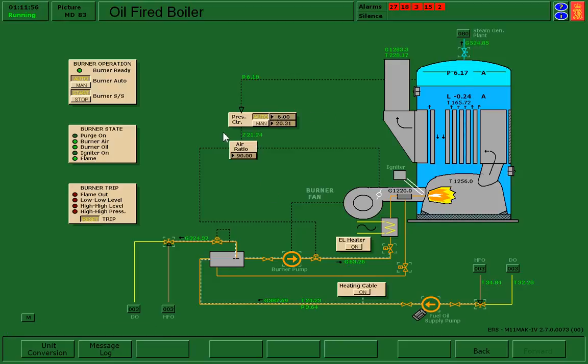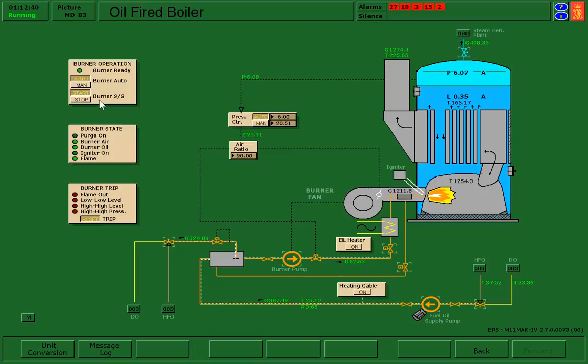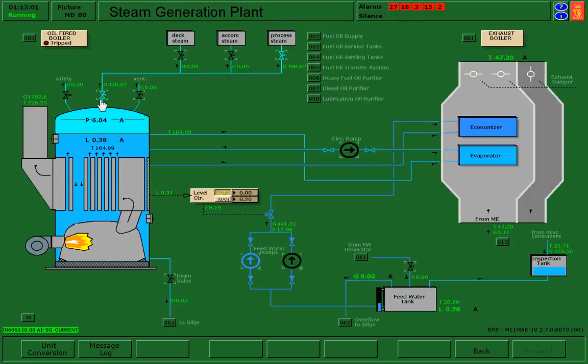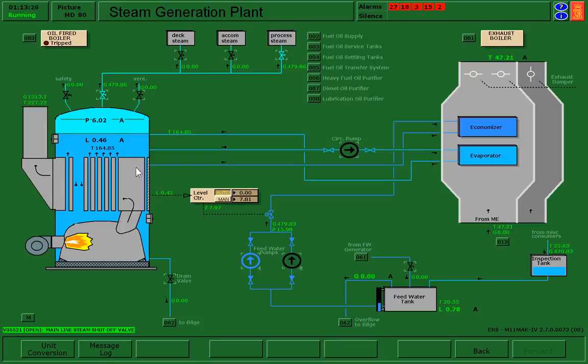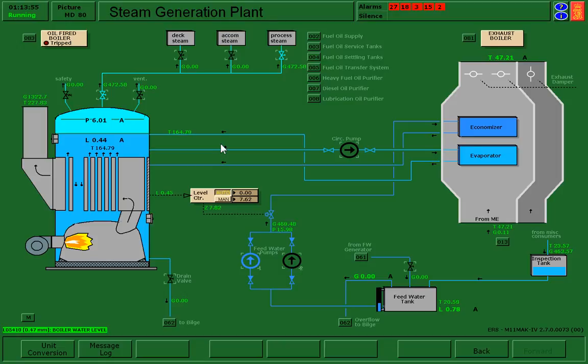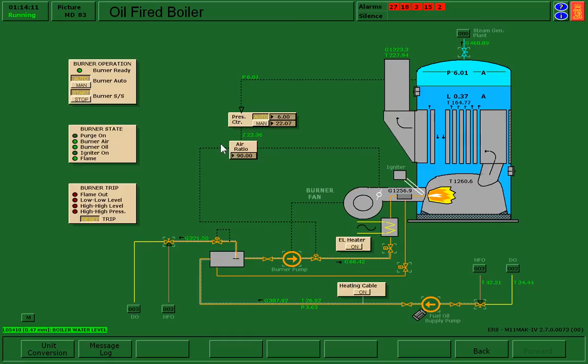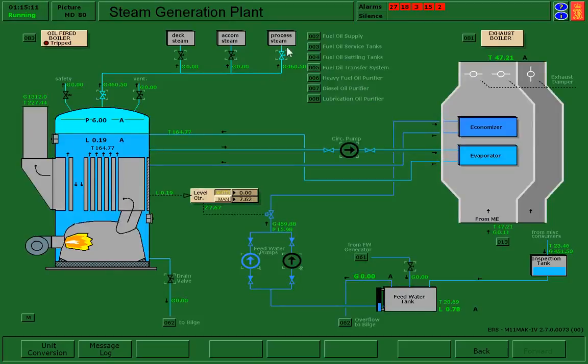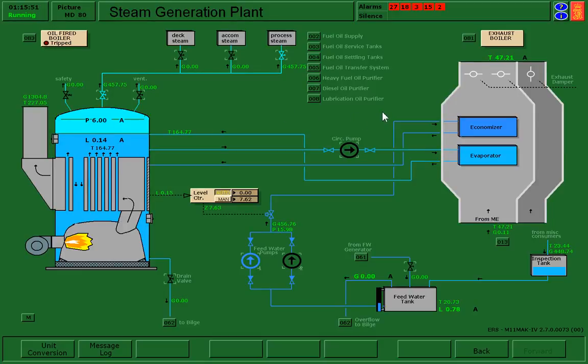Before we walk away, we just want to make sure everything is in auto. Number one priority is going to be this in auto. He's going to be able to turn off the burner if we have a problem. Our second priority is going to be our level controller and pump are active, so we don't want to have a case where we have too high or too low of water level. And then our third priority would be that our pressure controller is in auto. At this point, we can move on to using our steam in other places. So if we want to send steam to other processes or other functions inside of the plant, then we can start to get those systems started.